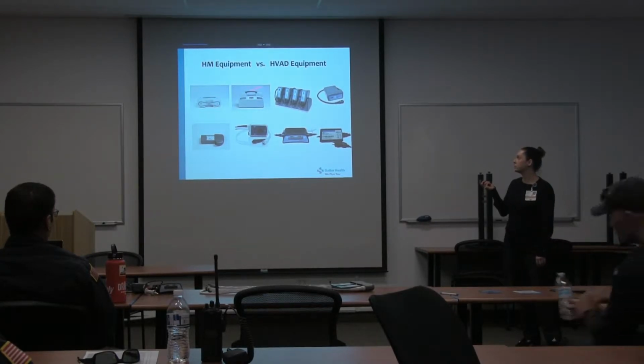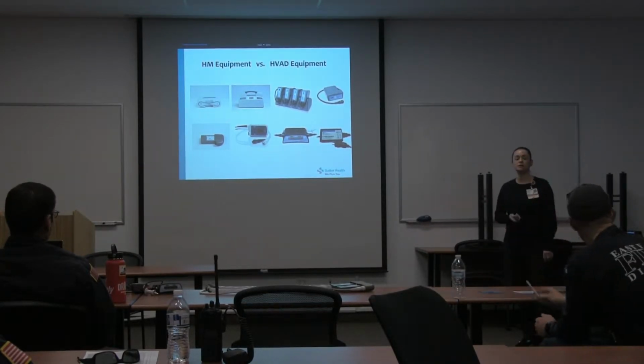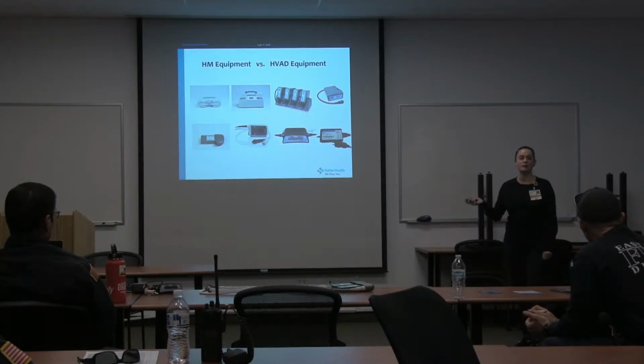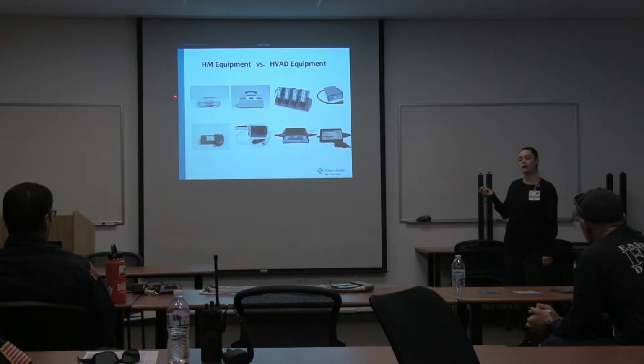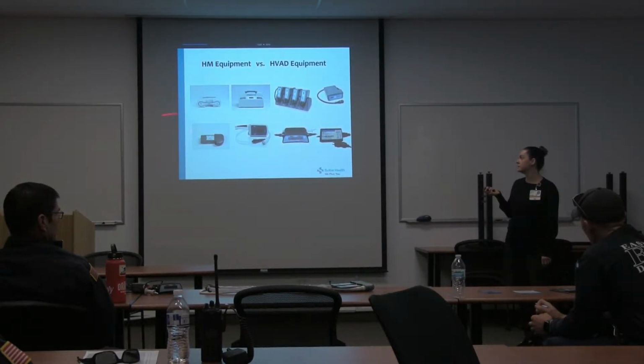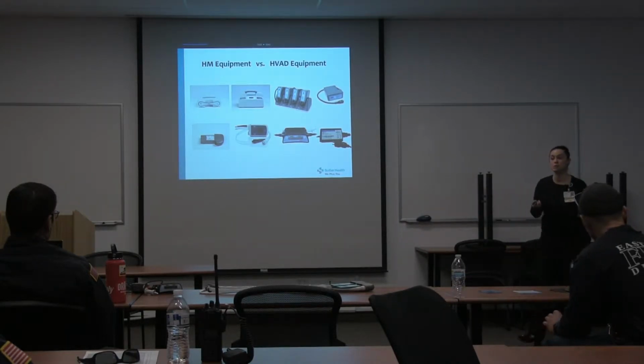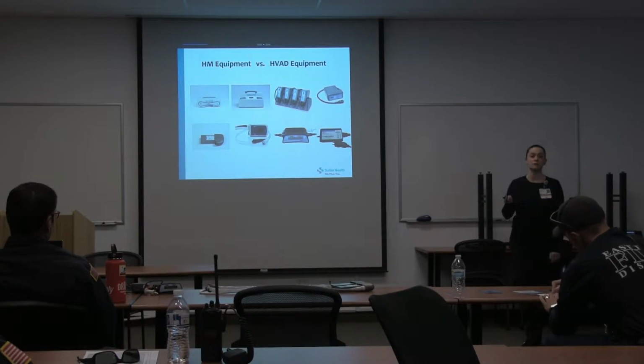The Abbott Corporation for the HeartMate gives them a power box, and they directly plug themselves into the wall at night to get constant AC power, so they're not sleeping with these clunky batteries on them and worrying about getting battery alarms. So they have an ability to plug into the wall at night, and it gives them a long 17-foot cord that they can connect to. And then during the day, they're on 2 batteries, mobile, walking around. All the batteries for both companies, when the patient locks and loads in the morning, last about 16 hours, so all day long before they have to change their batteries.